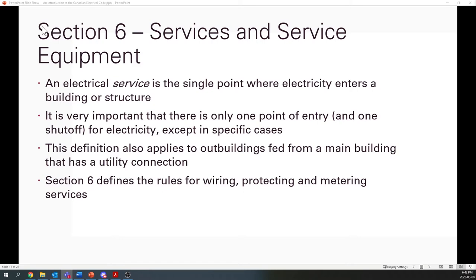Or another way of looking at it is a service is still a service wherever it is, regardless of the amount of fault current that's available at that building or location. You're going to have much more fault current available at the utility connection, but much less, of course, way down the line. Regardless, it's still a service way down the line.